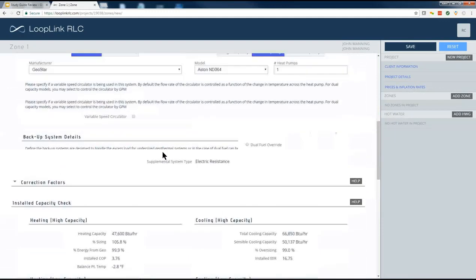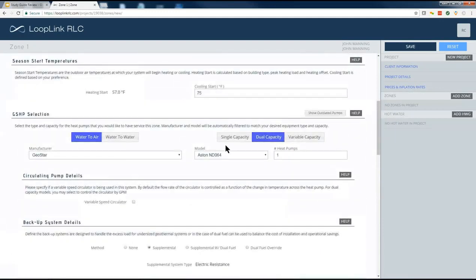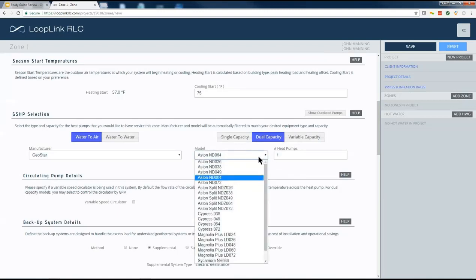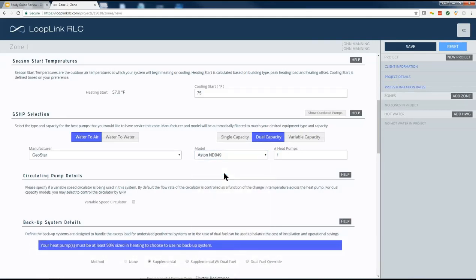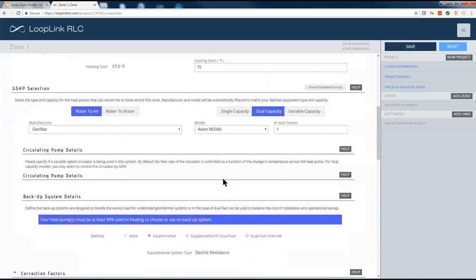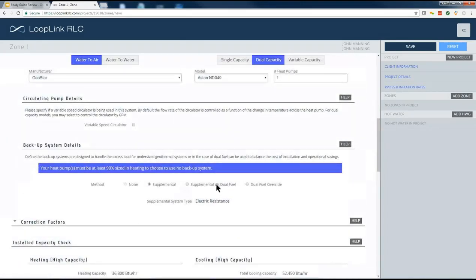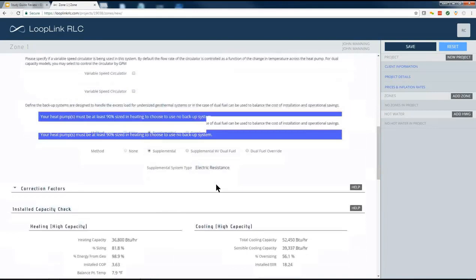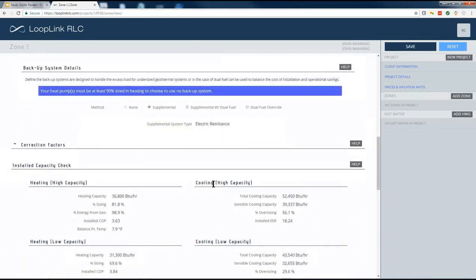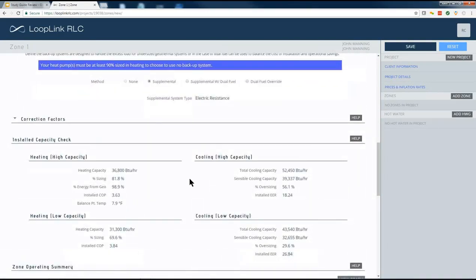But just say, for the sake of example, let's go up here and maybe flip to the next smallest unit just to see what that would look like. Obviously, when we go to a smaller unit, it's going to be slightly undersized relative to the heating load. I'm going to go ahead and grab an ND049, which is that 4-ton dual capacity unit. Let's scroll down and take a look at what that looks like. So now we're at our 4-ton unit. And you can see relative to the peak heating load, we're only about 80% sized.